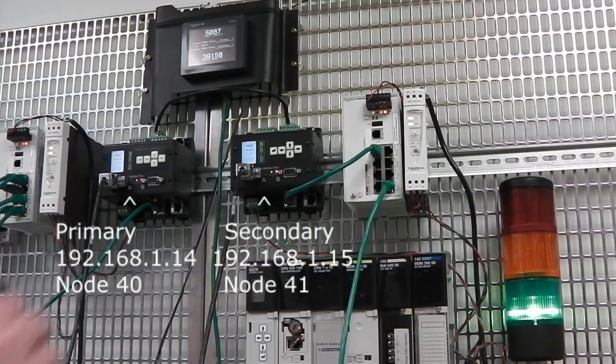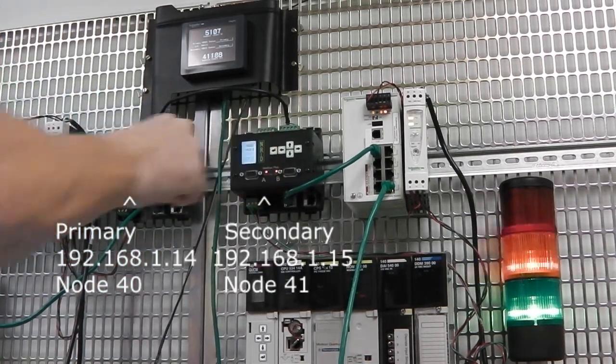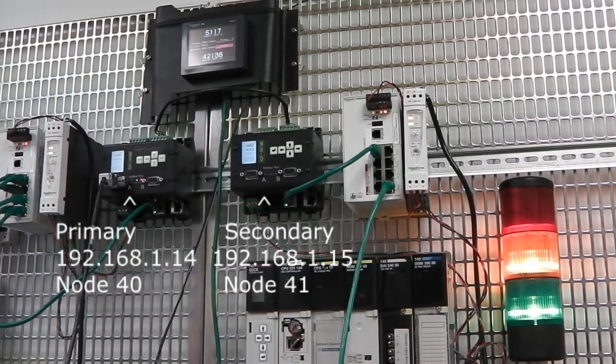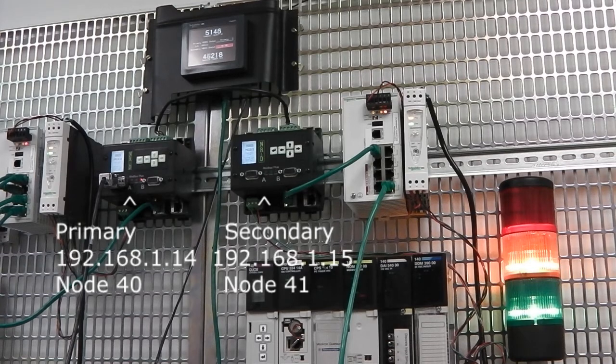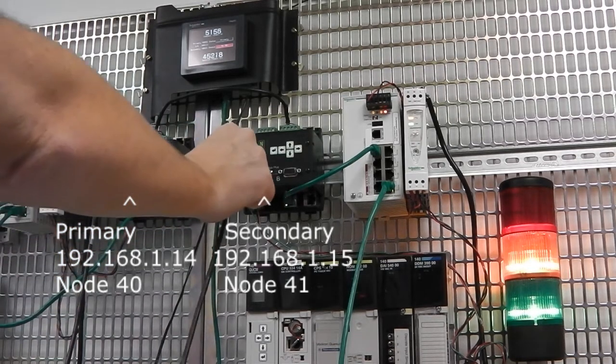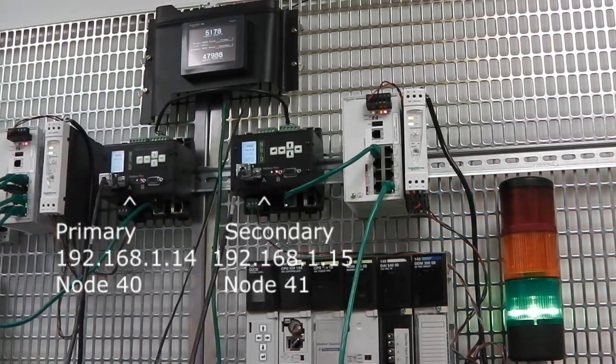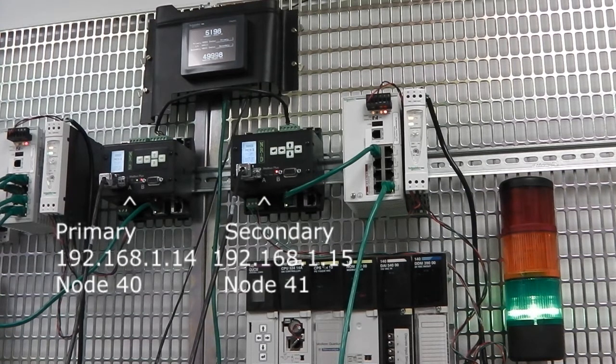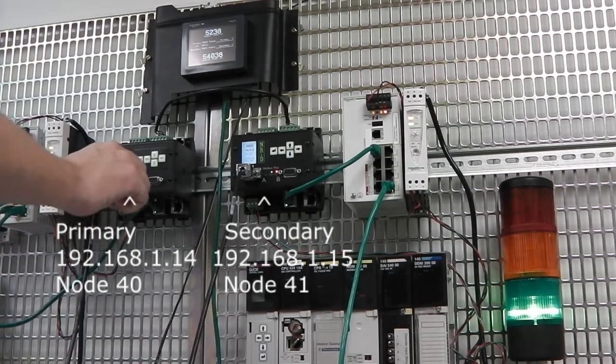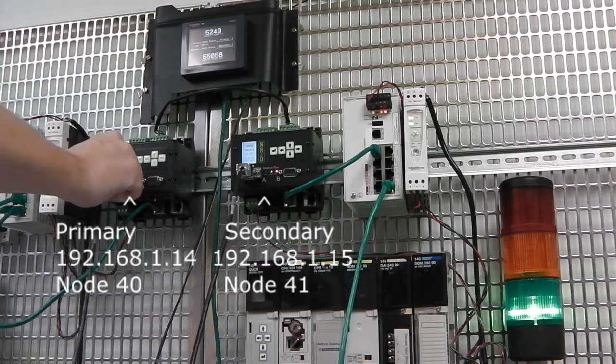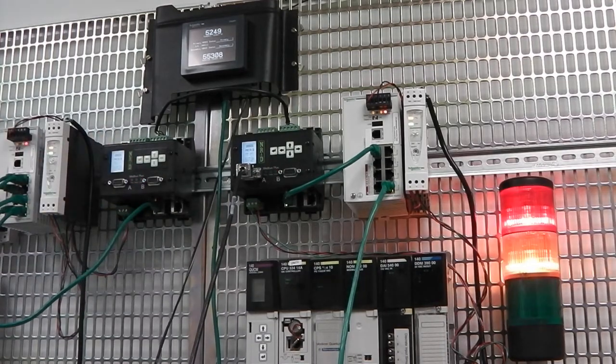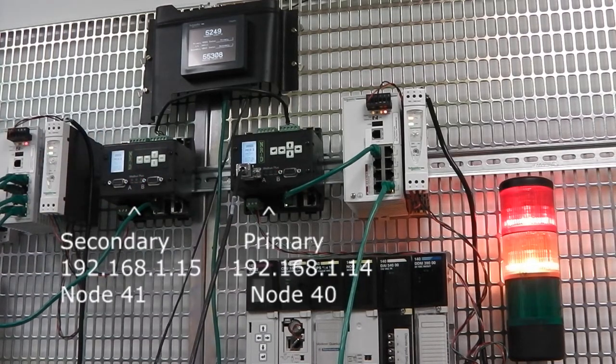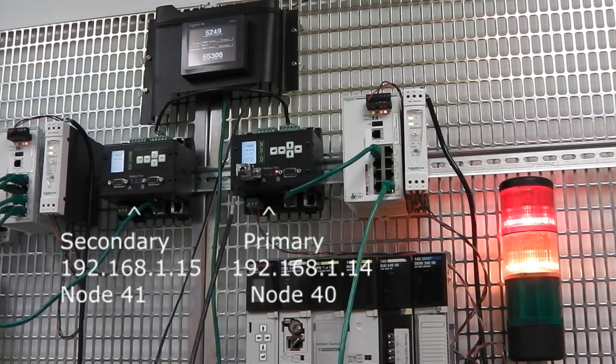Removing the Modbus Plus cable from the primary triggers a transfer. The secondary unit now becomes the primary and assumes all communications.